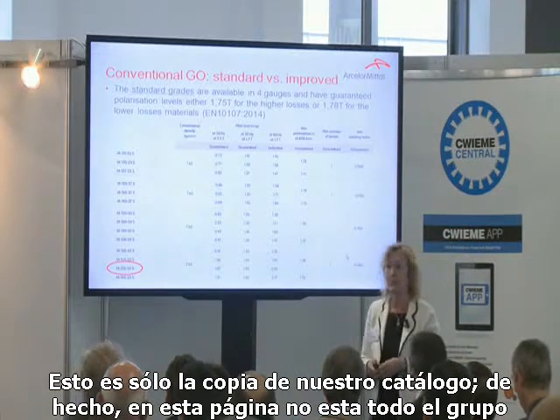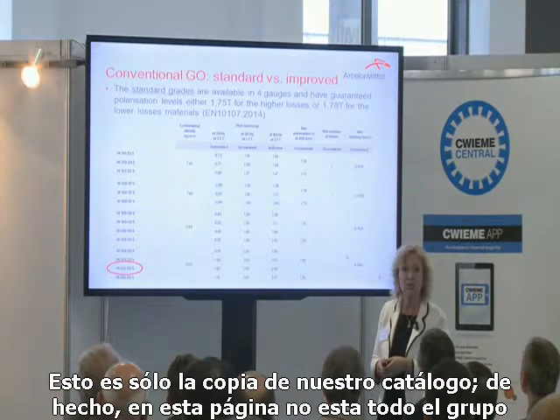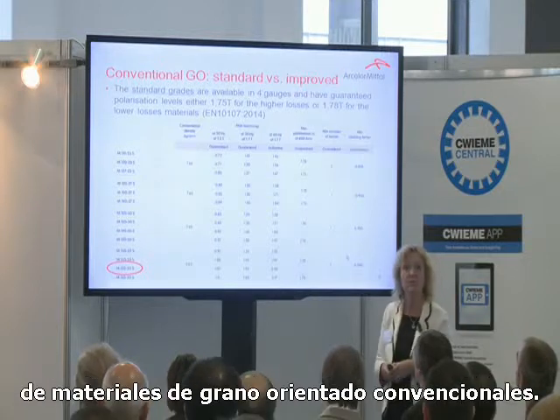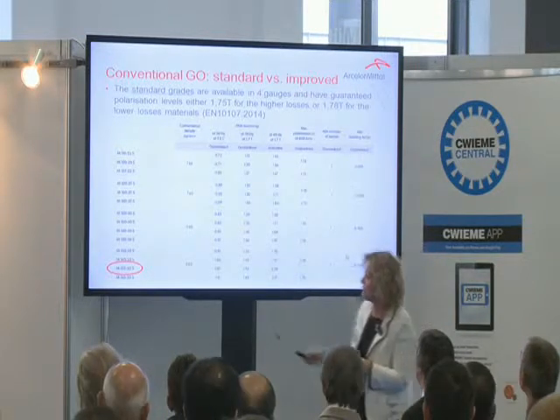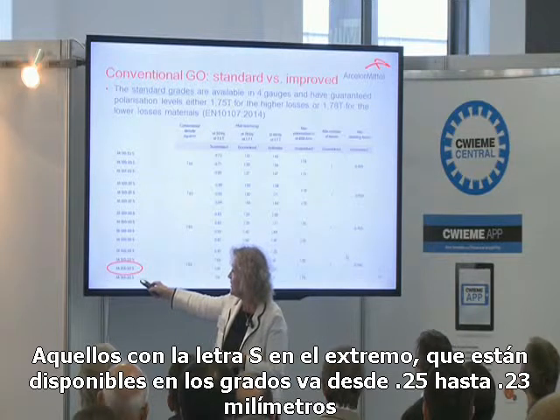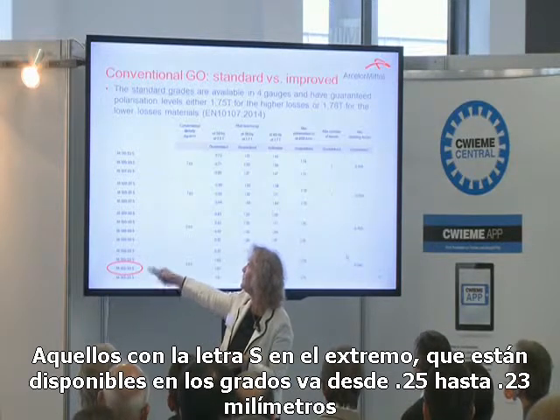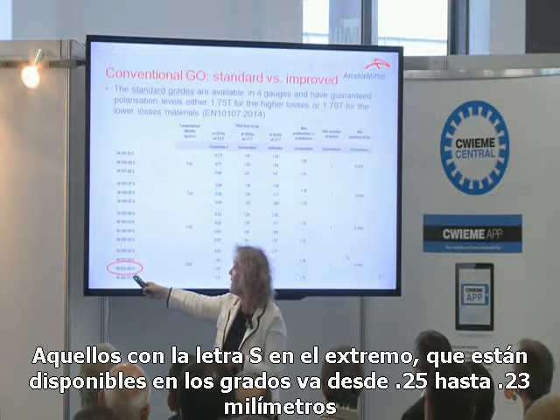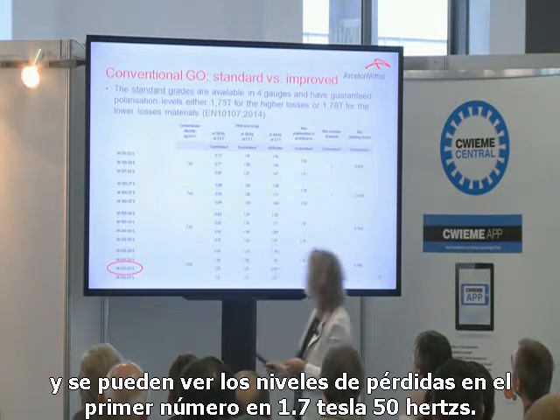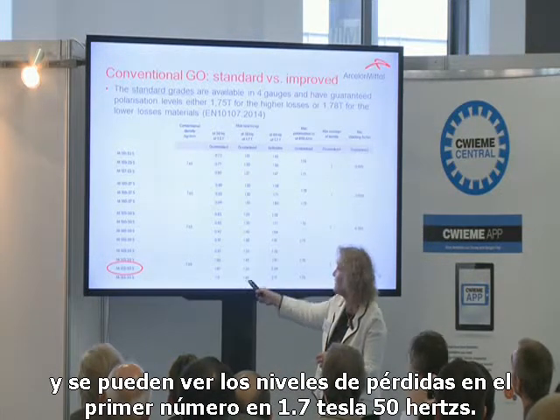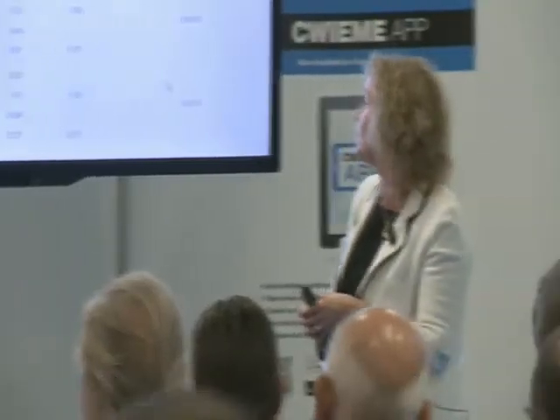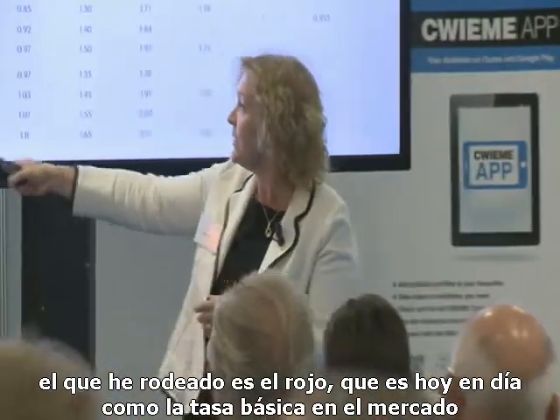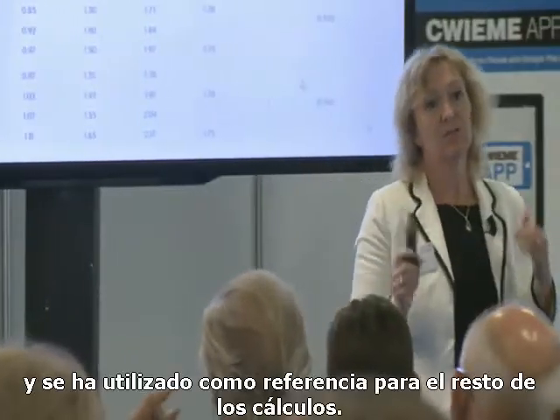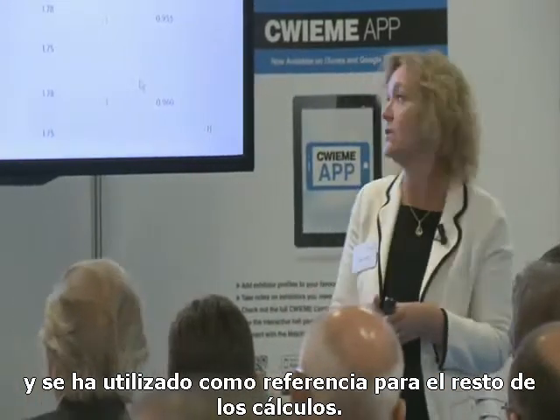This is a copy of our catalog. This page covers the whole group of conventional grain-oriented materials, those with a letter S at the end, available in thicknesses from 0.35 to 0.23 millimeters. You can see the loss levels in the first number, at 1.7 Tesla and 50 Hertz. The one I've circled is the red one, which is nowadays the basic grade in the market, and it's used as the reference for the rest of the calculations I will show.